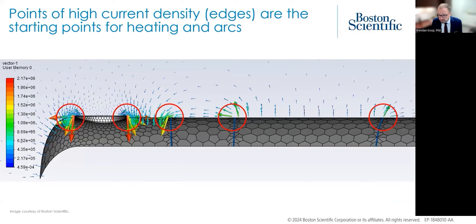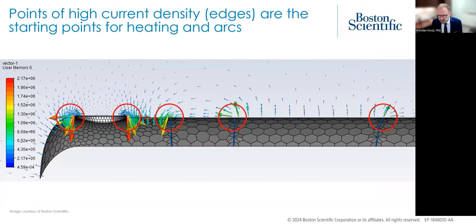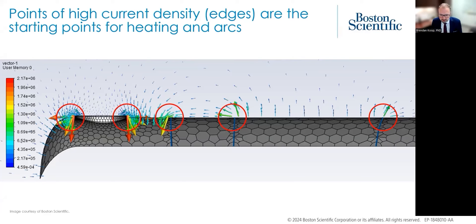That very high field is one of the reasons we do see some transient effects in other tissues, and something we keep close eye on as designers. The way to help make the situation better is to change the spacing of electrodes and change the surface area of the electrodes — these are the things we try to design for to minimize these effects. When looking close to the electrodes, we keep a close eye on the edges, how close the edges are to each other, how much the edge is exposed to the environment, what the length of the edges is — these are where current density is highest. Most of the bad things we're trying to avoid start at these edges: heating, arcing, red blood cell aggregation. With purposeful design, we can minimize these effects by playing with electrode spacing and surface area, building that in from the beginning.